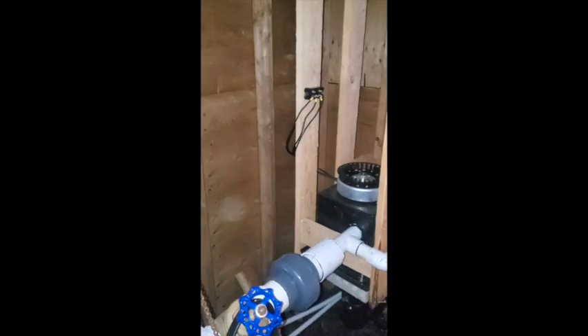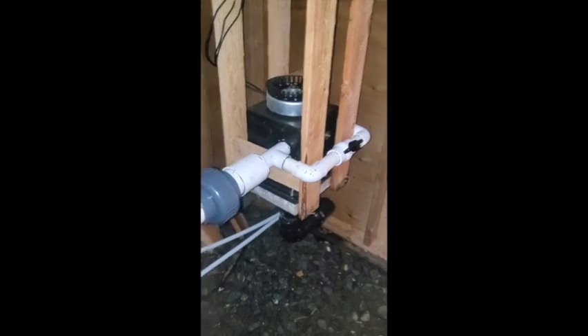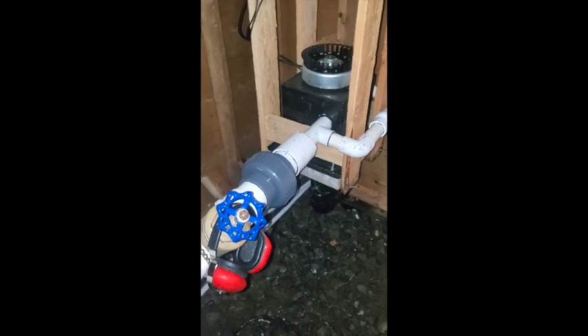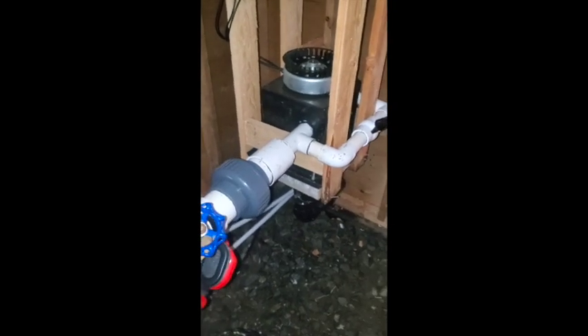We are back in the powerhouse after about a week of personal recovery time. Last time we had it running for about two hours and got 200 volts. I just went into the turbine and cleaned it out one more time and found this in the second nozzle — probably the biggest piece we've found yet. I'm hoping keeping it on for two hours flushed everything out and that was the last piece we're going to get.